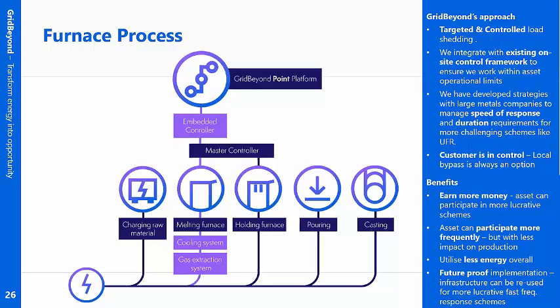We're constantly monitoring your critical parameters, temperatures, and it's not an exact science. It's back and forward between us and you. You might have a very tight window of temperature control, for example, 80 to 82 degrees. If it's outside those thresholds, you're not available to us. Well, that mightn't work because you might never be available then. So it's finding that sweet spot where we don't hurt your process and we have you available for as much as possible for grid schemes. If you want to go on again, Wayne.